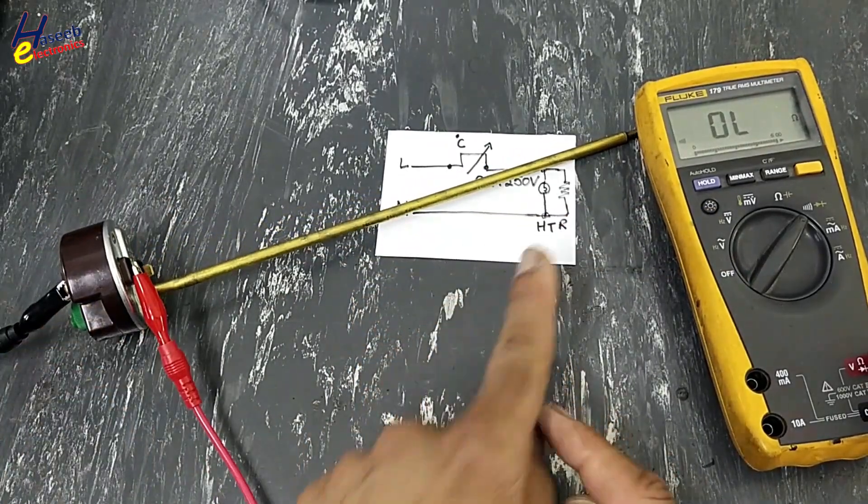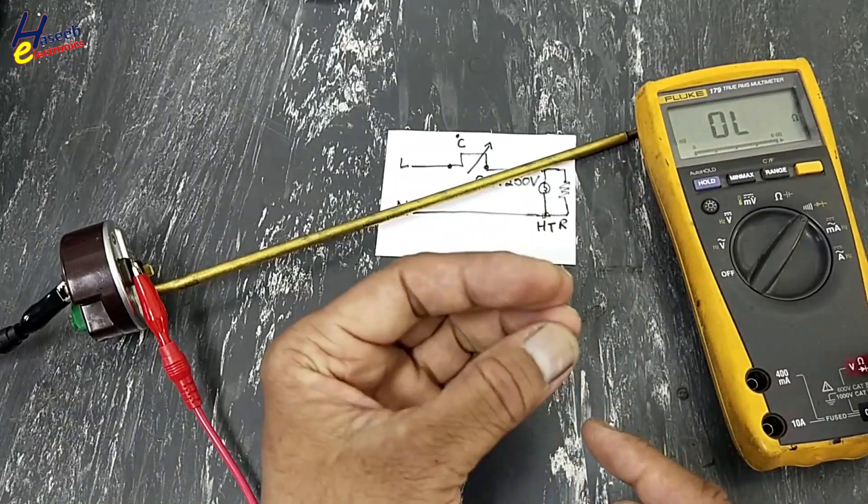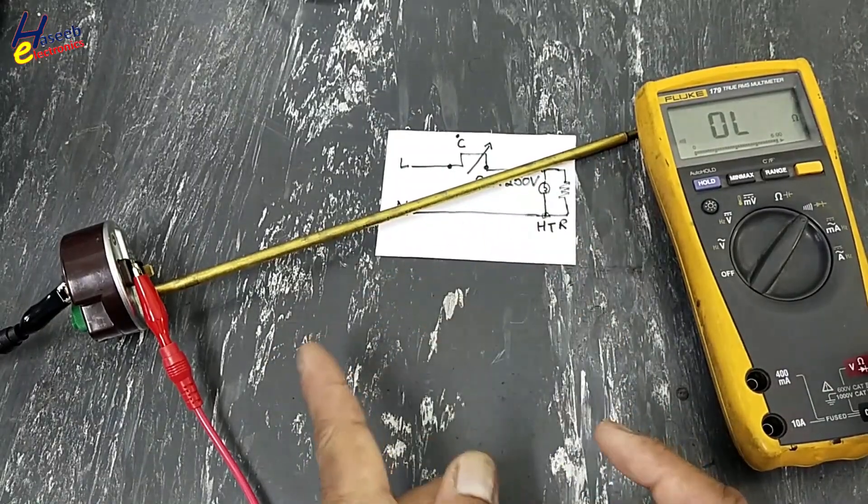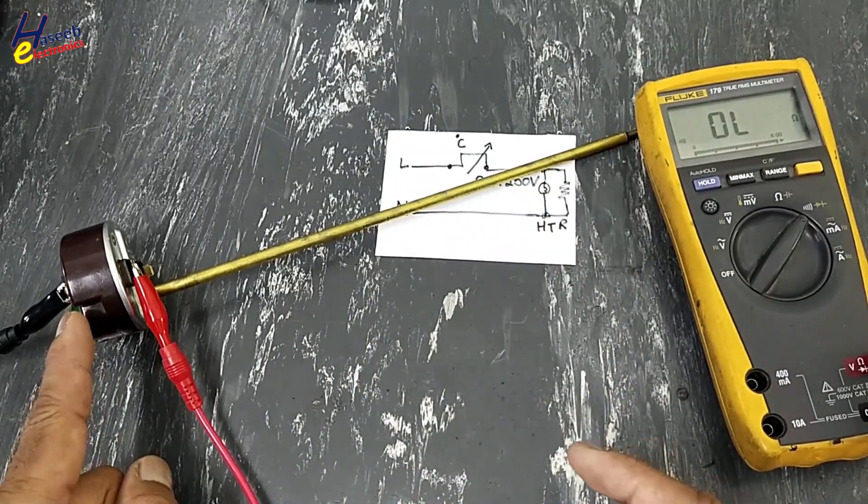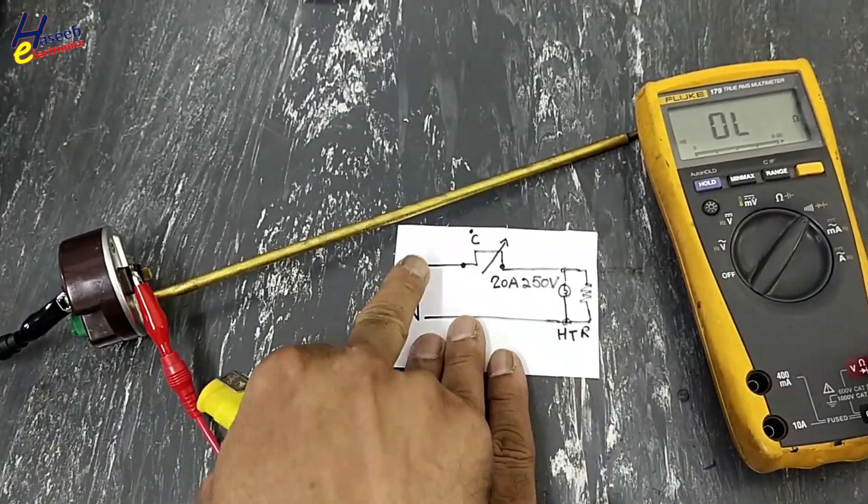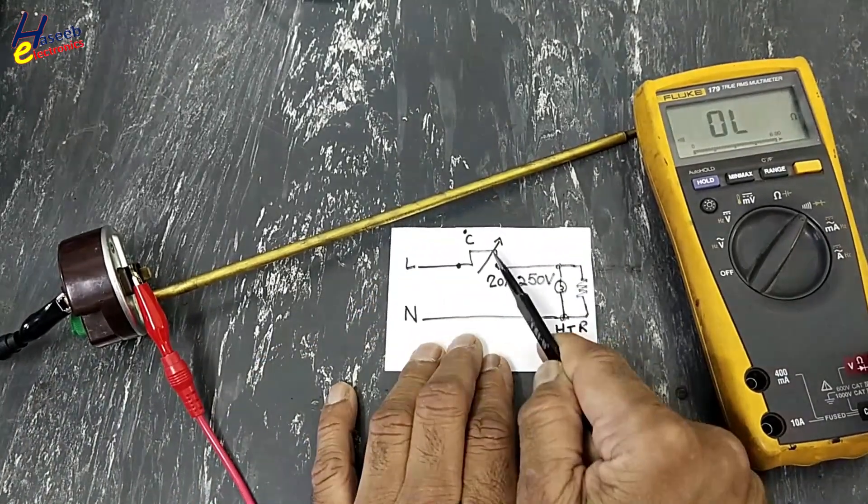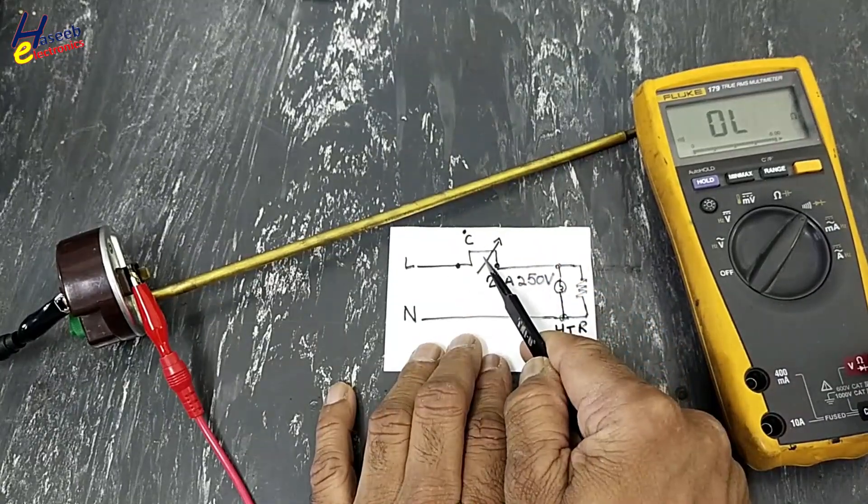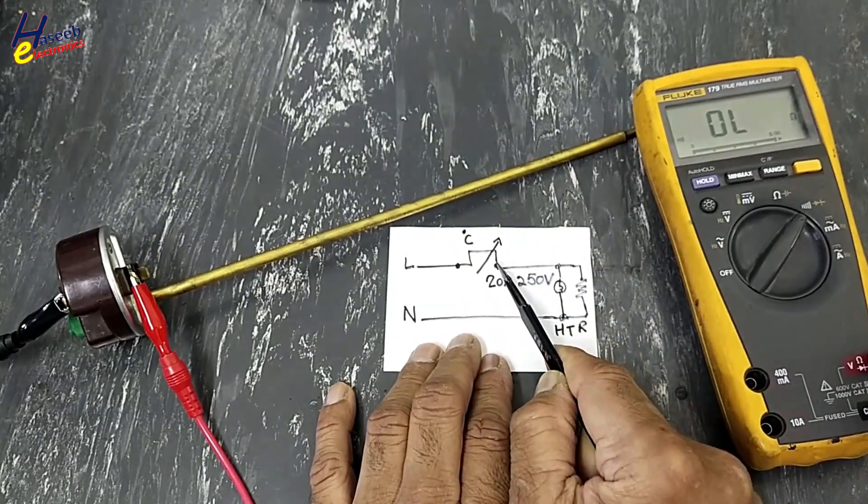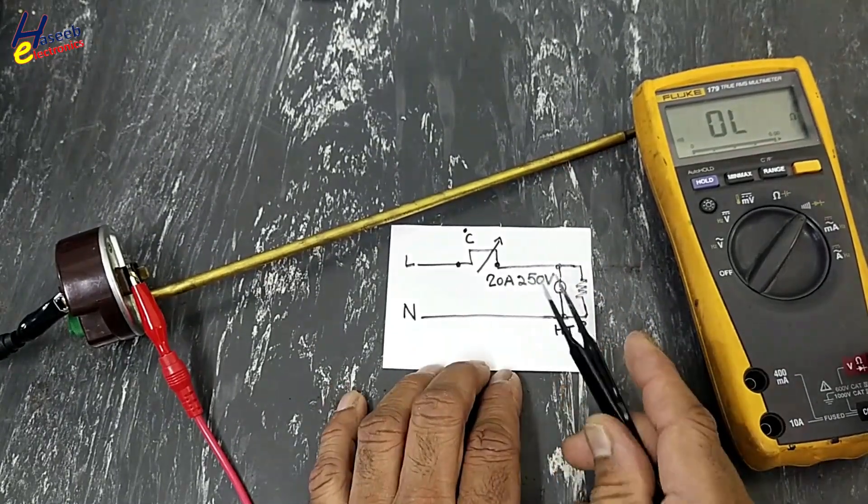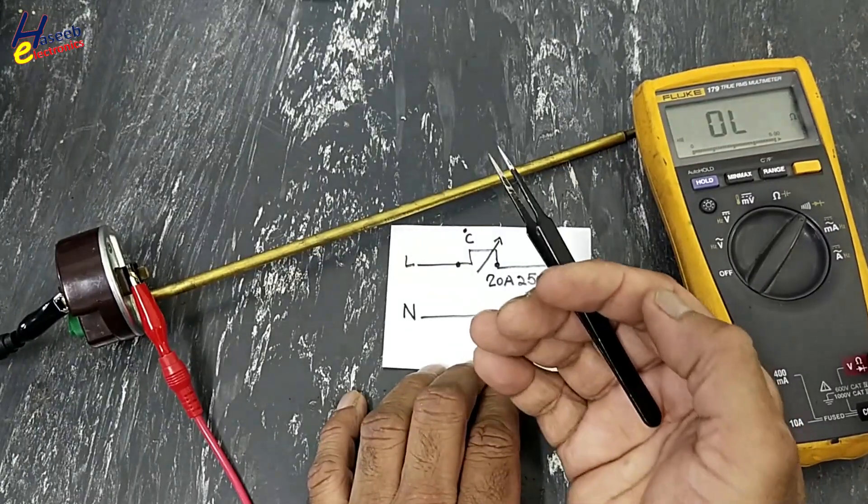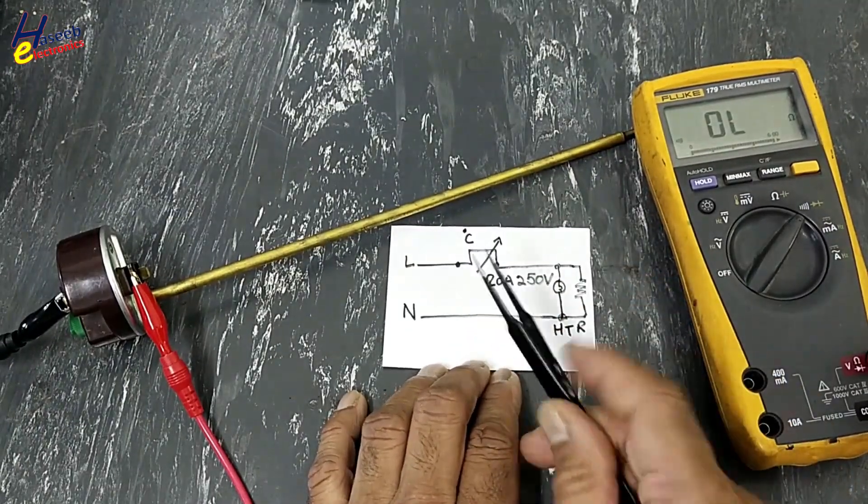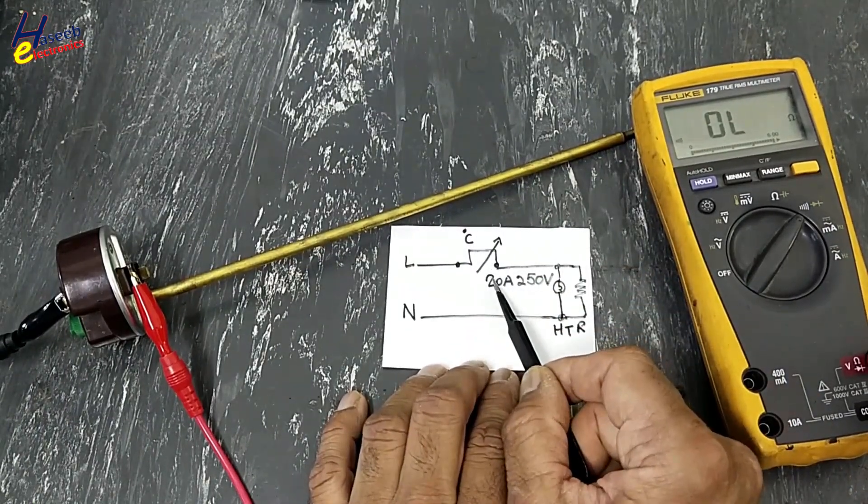And we will wait until its temperature is decreased and it will turn on again. That time it will pass the current to the heater. When temperature will increase, gas present in this tube will push this switch to turn off, so it will turn off. When it will cool down, the gas pressure will return back to normal, so switch will make again.